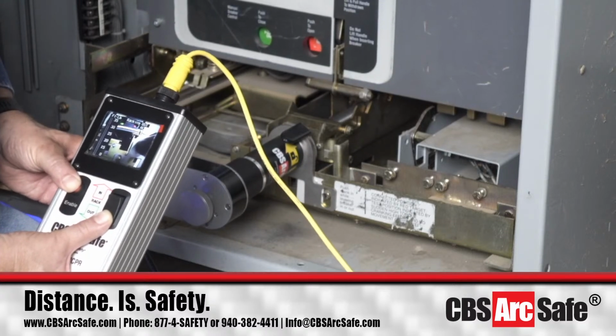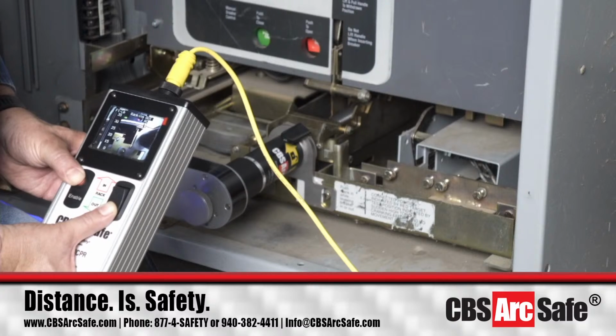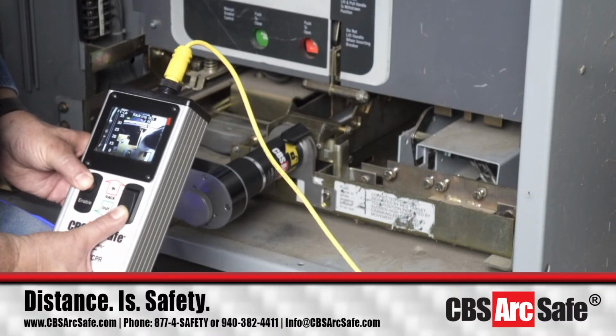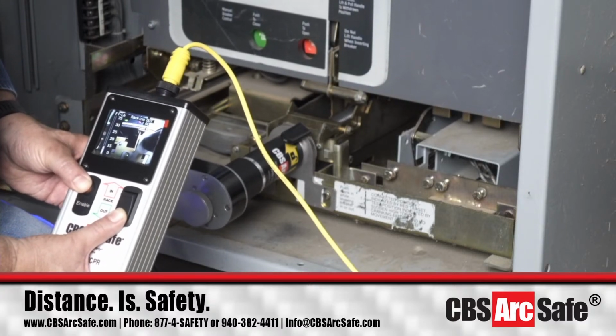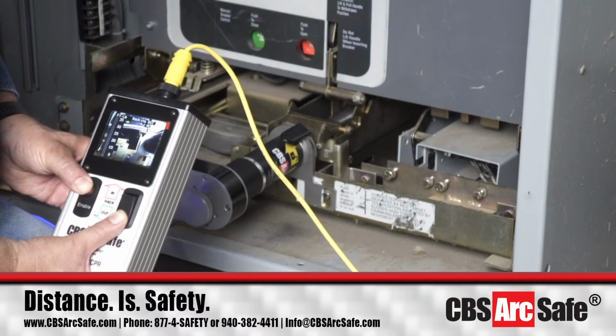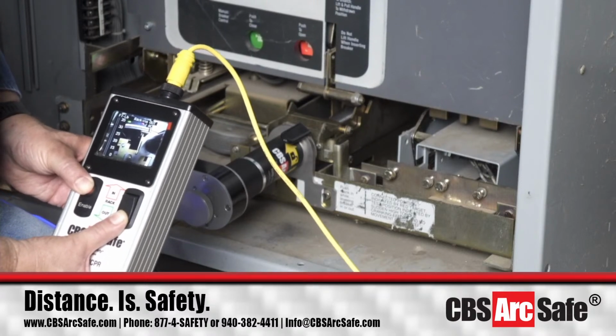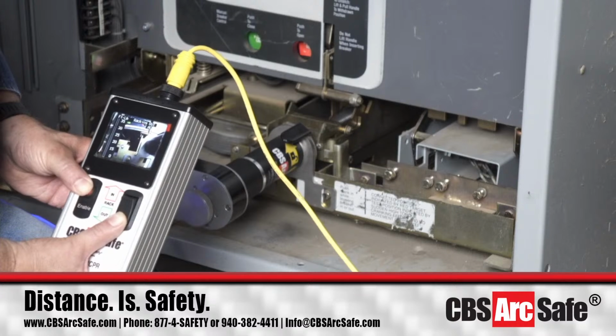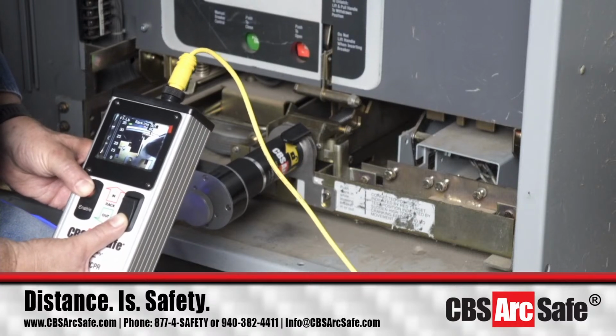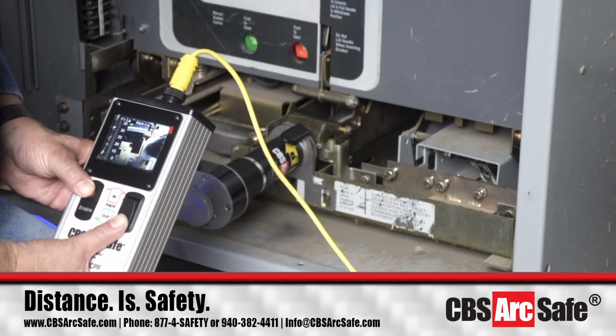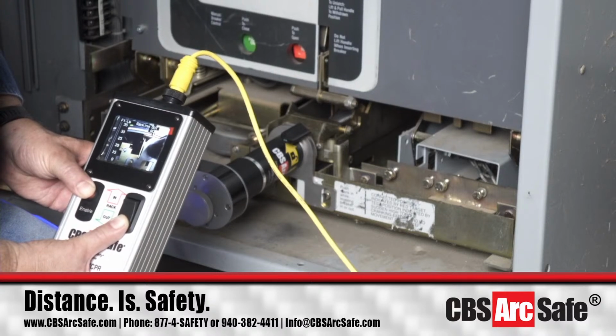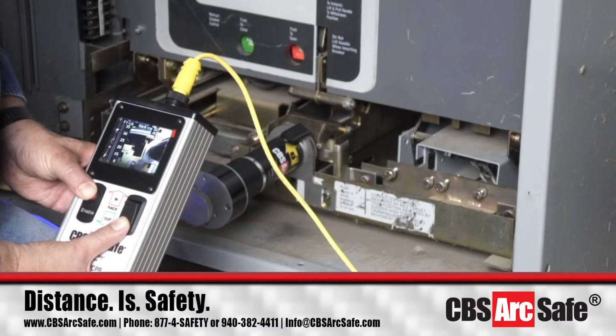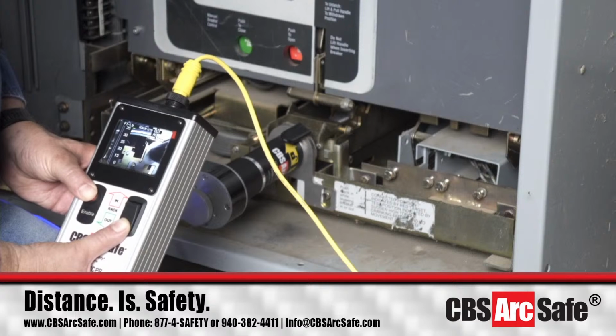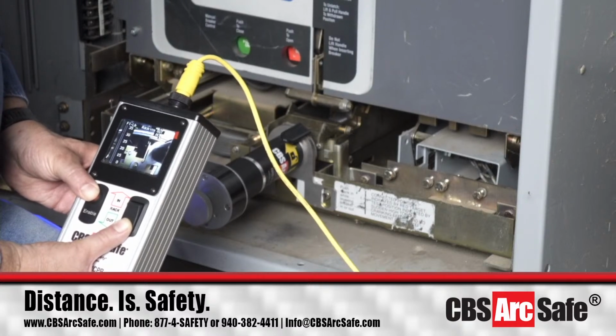Say again? The torque, there's an indicator on the right side, or correction, left side of the display, displaying the torque as the breaker moves right now. One of the things to note is, up until the time that the breaker contacts the bus, we really shouldn't be seeing over like 5 to 10 foot-pounds of force as it moves. Okay? So this is going to bring it all the way out.